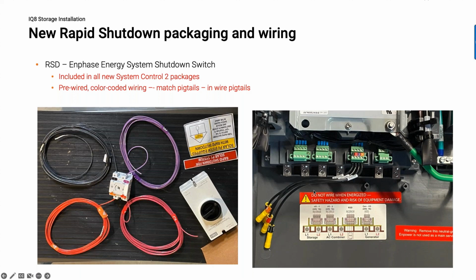When you're going to commission the system, before you energize it, just take a meter and put it on ohms, and you should see with the switch in the operational position, 1 and 2 should be shorted, and 3 and 4 should be shorted. Okay? If 1 and 2 are open, or 3 and 4 are open, then your system's not going to work, and you should fix the wiring before you try energizing the system, because you're going to end up having to shut it down anyway to correct the wiring. Okay.